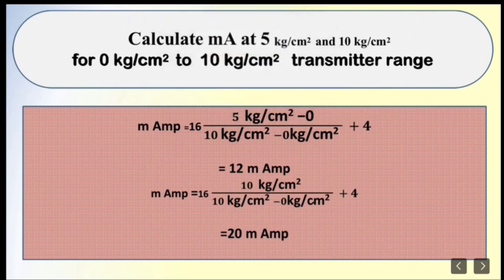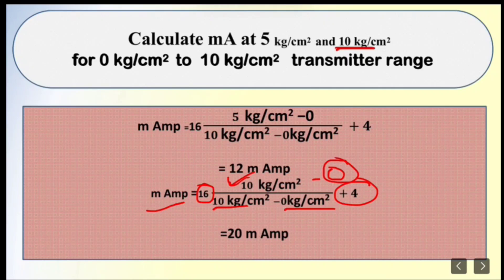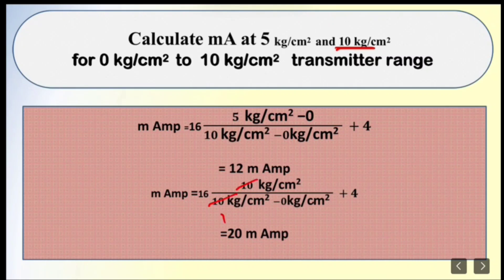Now let's calculate for 10 kg/cm². mA = 16 × (10 − 0) / (10 − 0) + 4 = 16 × 1 + 4 = 20 milliamperes. So at maximum range (URV), the output is 20 mA as expected.